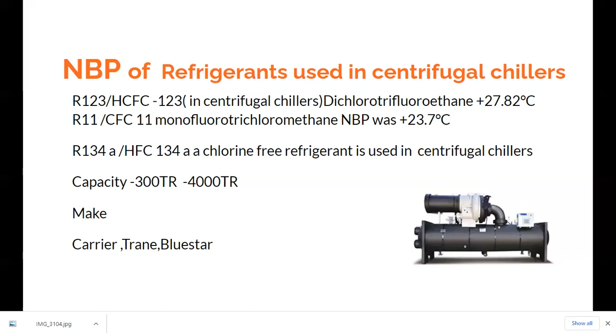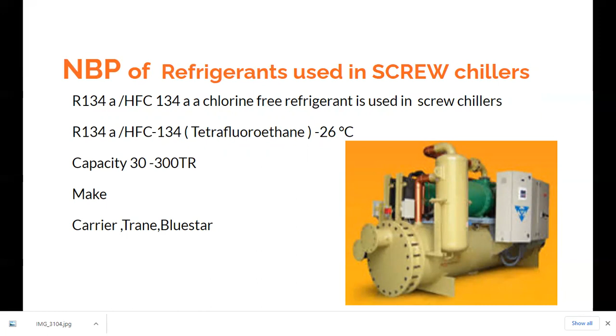You often find that R134A, which has a negative normal boiling point, is also used in centrifugal chillers nowadays. In screw chillers, a chlorine-free refrigerant, R134A, HFC134A, is commonly used. And tetrafluoroethane has a normal boiling point of minus 26 degrees centigrade. So look at this.